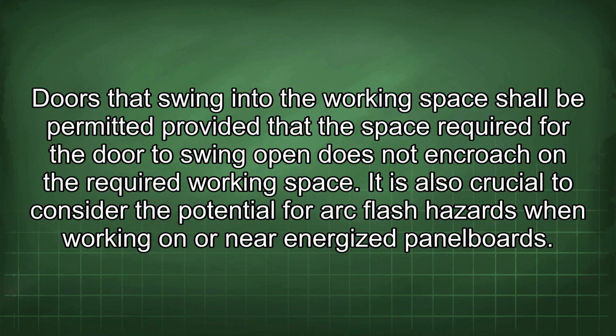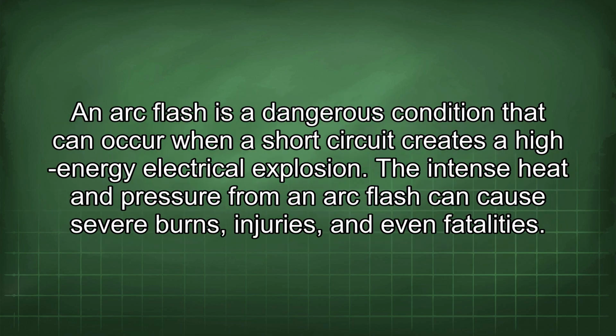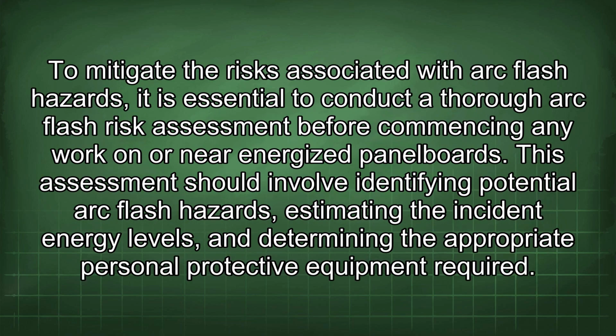It is also crucial to consider the potential for arc flash hazards when working on or near energized panel boards. An arc flash is a dangerous condition that can occur when a short circuit creates a high-energy electrical explosion. The intense heat and pressure from an arc flash can cause severe burns, injuries, and even fatalities. To mitigate the risks associated with arc flash hazards, it is essential to conduct a thorough arc flash risk assessment before commencing any work on or near energized panel boards.